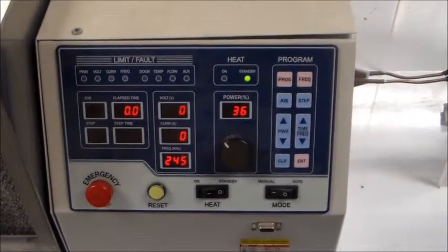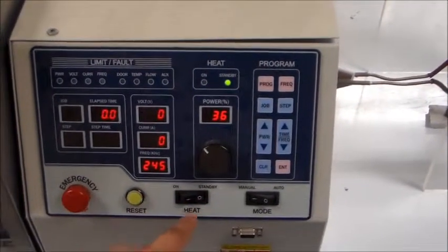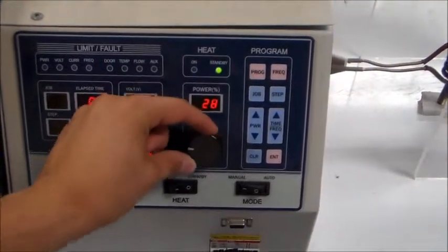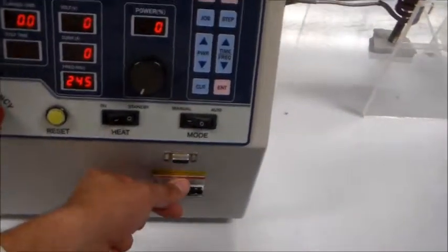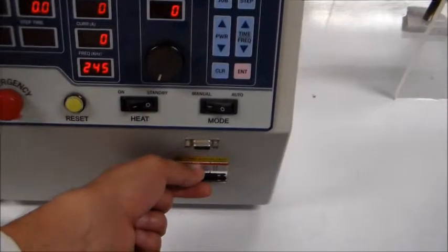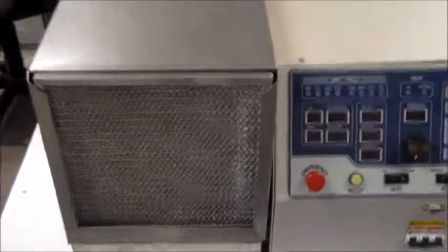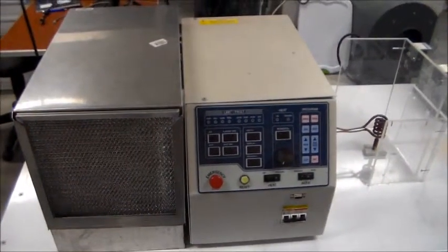If you are done with your test, make sure the switch is in the standby position. Turn the power knob to zero position and move the main power breaker downwards. This will shut down the machine. Now, leave the water pump on for the required time to cool down the system.